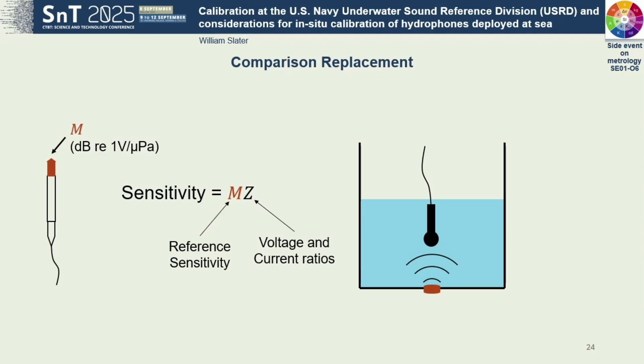Once we have a calibrated reference hydrophone, we calibrate other transducers by comparison, which is less involved. We can do a side-by-side comparison at low frequencies where we know the acoustic pressure is the same at the location of the reference and the unknown hydrophones. At higher frequencies, we measure the acoustic pressure at a point in the medium with our reference, essentially calibrating the projector. Then we replace the reference with the unknown hydrophone at the same spot.